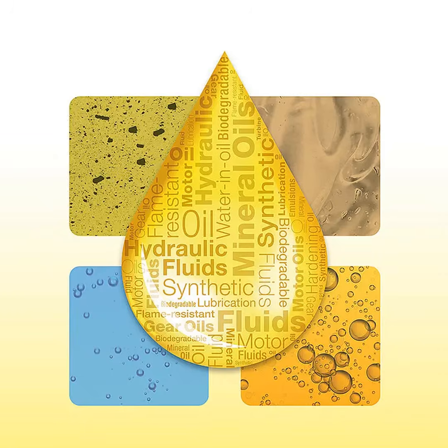Now that we've explored where contamination comes from, let's talk about the different forms it can take. The first, and probably most familiar, is solid contamination. Solid contamination includes things like grinding material, rust particles, welding scale, steel particles, iron, bronze, aluminium, fibers from cleaning cloths, rubber debris from hoses and seals, oxidation residue, and particles generated from bearing materials.